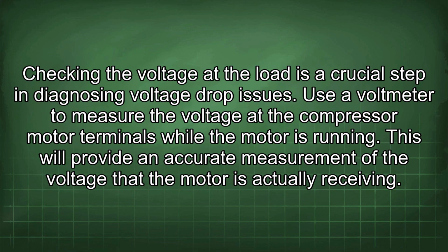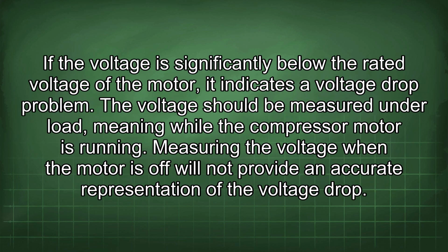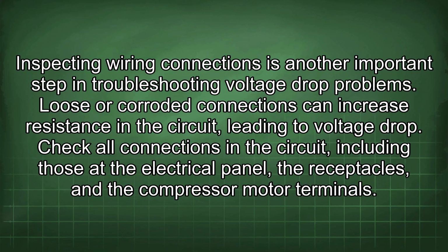Checking the voltage at the load is a crucial step in diagnosing voltage drop issues. Use a voltmeter to measure the voltage at the compressor motor terminals while the motor is running. This will provide an accurate measurement of the voltage that the motor is actually receiving. If the voltage is significantly below the rated voltage of the motor, it indicates a voltage drop problem. The voltage should be measured under load, meaning while the compressor motor is running. Measuring the voltage when the motor is off will not provide an accurate representation of the voltage drop. Inspecting wiring connections is another important step in troubleshooting voltage drop problems.